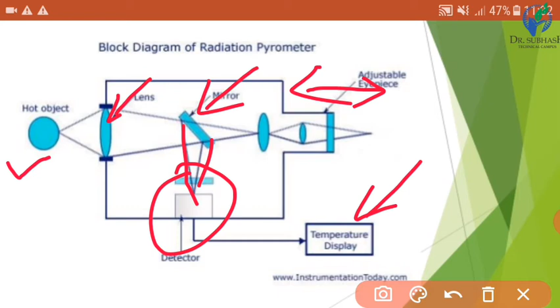So here we can see the block diagram of the radiation pyrometer. Here we can see the hot body, then the lens is there, and the lens will be focused on this. By adjusting this mirror we can focus to the detector, and we have already seen the detector may be the thermopile or thermocouple or any other temperature transducer, and this is the adjustable eyepiece. Okay, so we can adjust the distance, and the output of the temperature detector is given to the temperature display. It may indicate the temperature, it may be used for recording purposes, or it may also be used for controlling purposes. That we have already seen before.